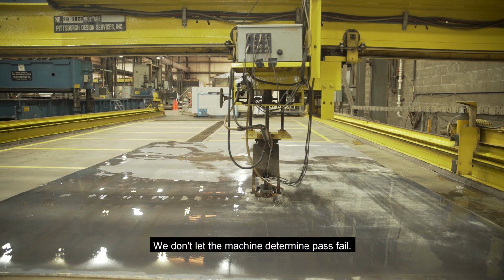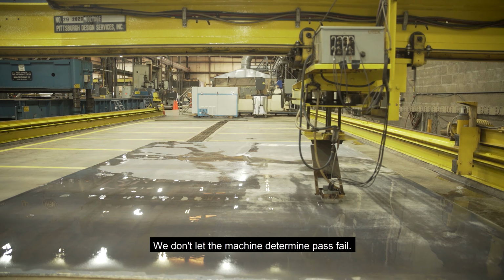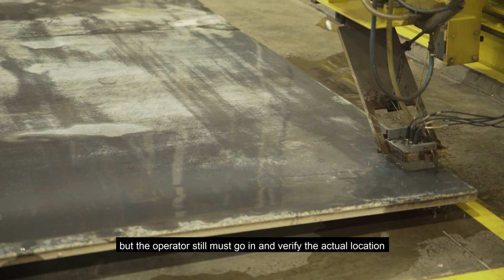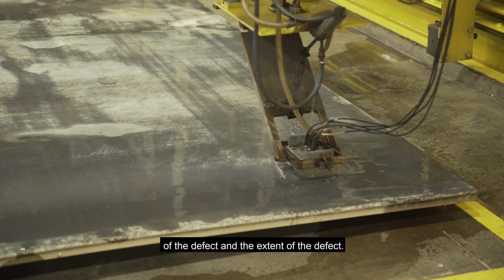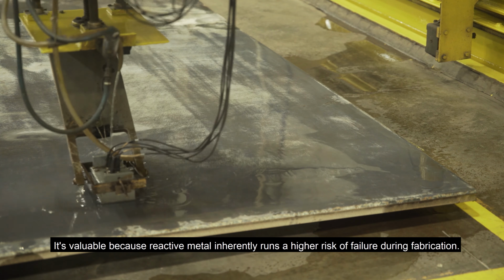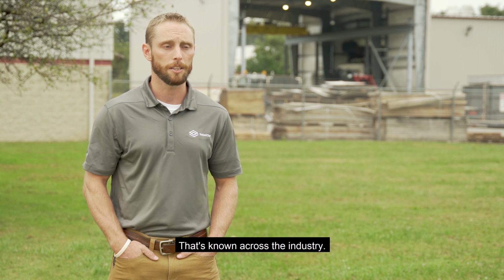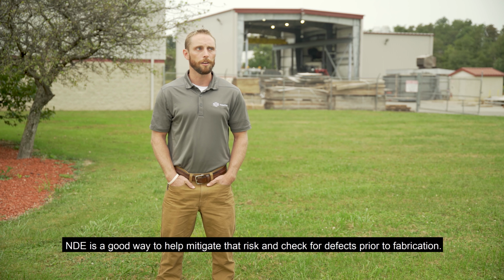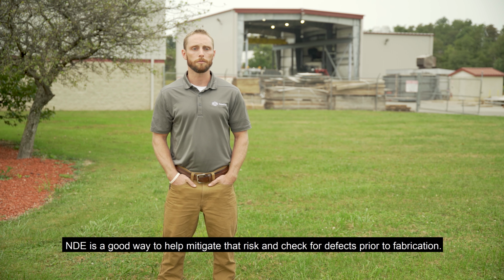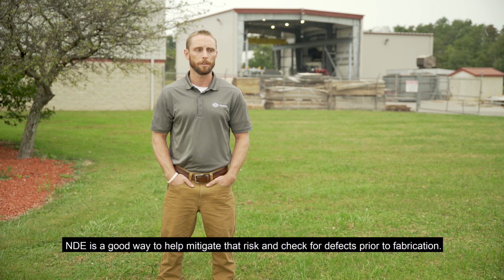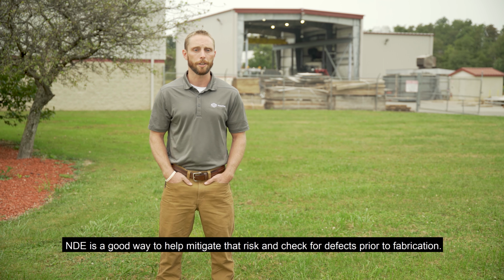We don't let the machine determine pass-fail. The machine is set up in such a way that it scans for gross defects, but the operator still must go in and verify the actual location of the defect and the extent of the defect. It's valuable because reactive metal inherently runs a higher risk of failure during fabrication. That's known across the industry. NDE is a good way to help mitigate that risk and check for defects prior to fabrication.